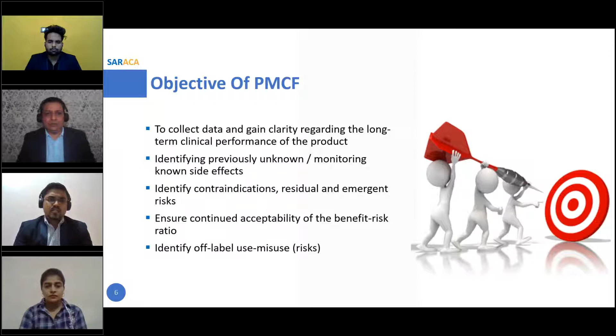So when to conduct a PMCF study? Nowadays, people are wondering when they should conduct a PMCF study. It applies to confirm the safety and or clinical performance for a new indication. Whenever there is a new indication regarding your device, you need to perform the PMCF study. Also for any changes to your medical device as well as to the labeling. If you have changed the device, the labeling, or the instructions for use, you need to go for a PMCF study.